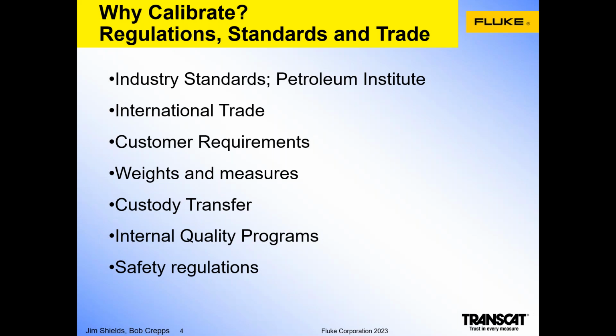So the error allowance in that particular process is very small, and records and calibration activities are required to ensure that the measurements on both sides of the equation, the entity delivering the gas and the entity receiving the gas, agree on the quantities, because a 1% error in this instance would be a significant amount of money and too much error for the financials. Another is the internal quality programs. The most common heard is the ISO 9000 program. I've heard it often stated that the technicians are going out to do their ISO calibrations, and those calibrations are documented as part of their quality program.